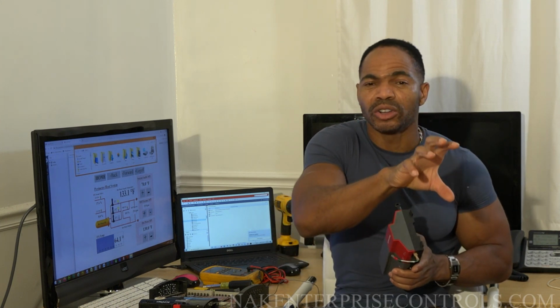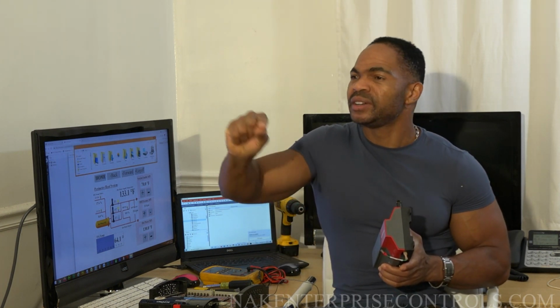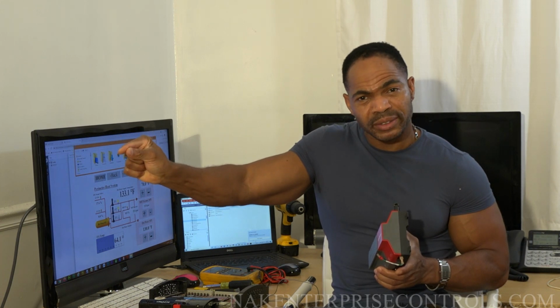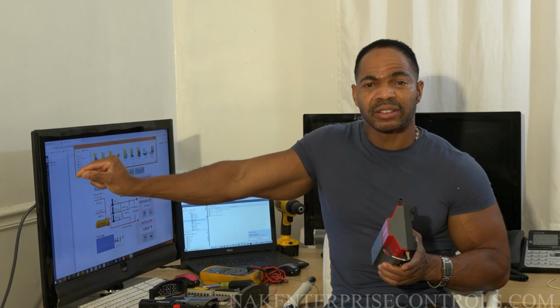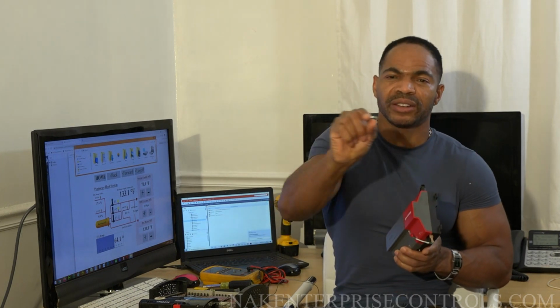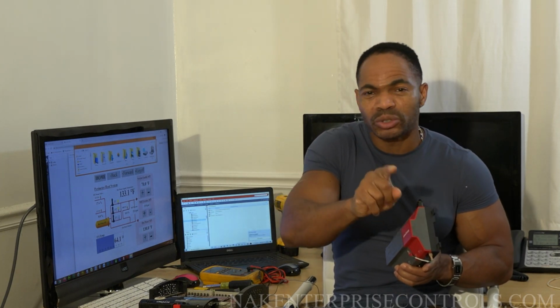You select a block called loop, you pull that block out, and then you pull a link from the block loop to your valve that you want to control. Then you pull a link from that loop to your temperature sensor that's in the room. Now the loop is seeing the temperature and it's also seeing your valve. You can have a separate set point created, where you pull a link from there to a set point. Say you say 72 degrees. So now that's telling the loop 72 degrees is where I want things to be.